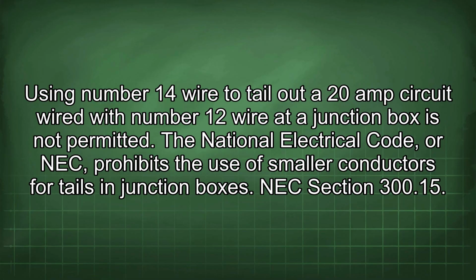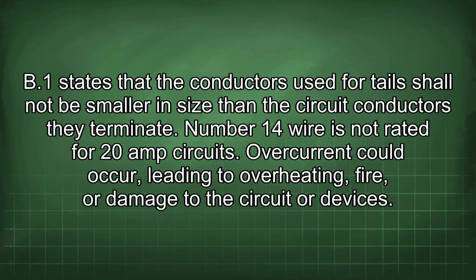Using number 14 wire to tail out a 20 amp circuit wired with number 12 wire at a junction box is not permitted. The National Electrical Code, or NEC, prohibits the use of smaller conductors for tails in junction boxes. NEC Section 300.15 B1 states that the conductors used for tails shall not be smaller in size than the circuit conductors they terminate. Number 14 wire is not rated for 20 amp circuits.